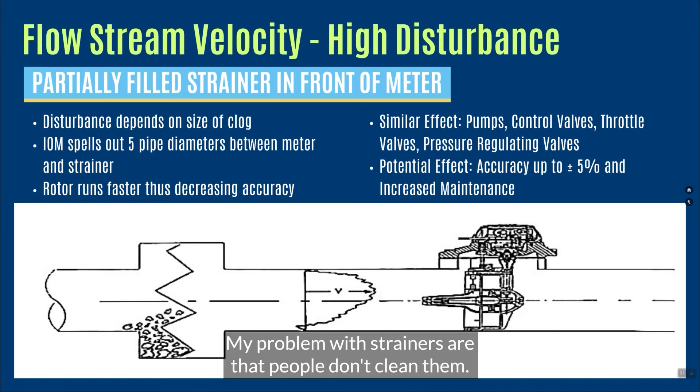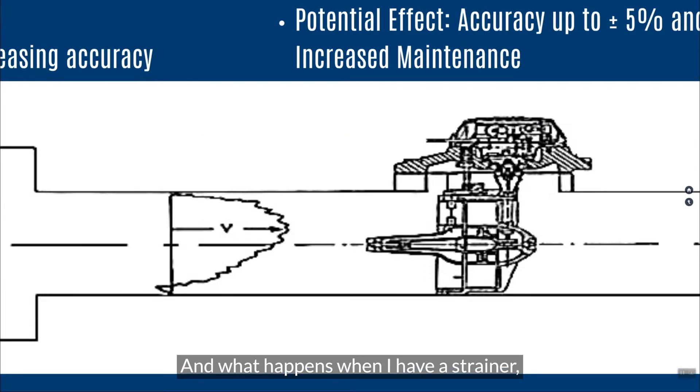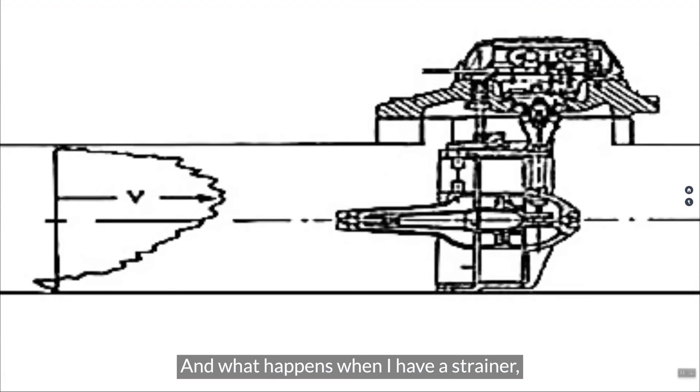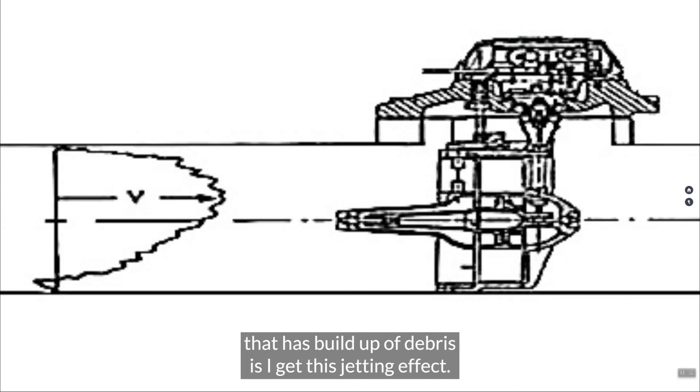Here's my problem with strainers. My problem with strainers are that people don't clean them. And what happens when I have a strainer that has buildup of debris is I get this jetting effect. I get this highly disturbed velocity profile that's jetting towards the top that's going to prematurely wear out your element.